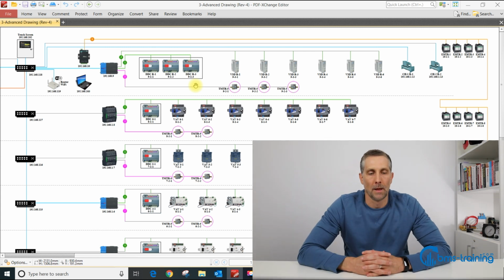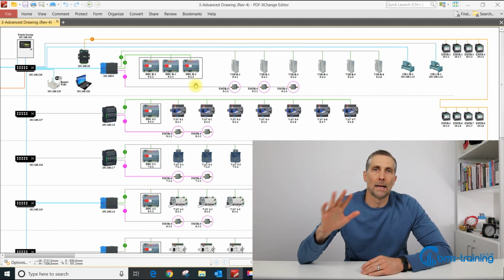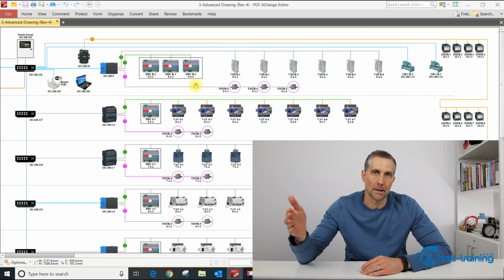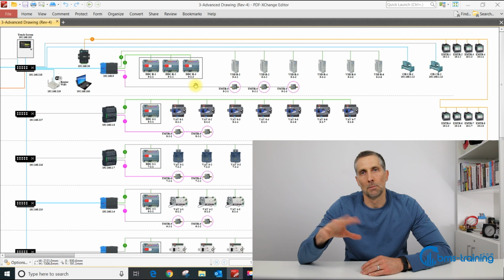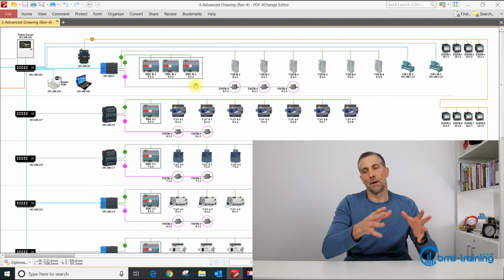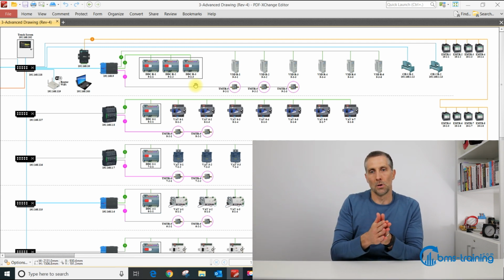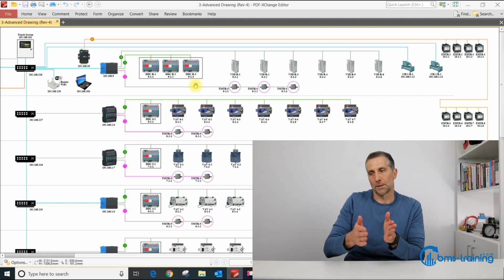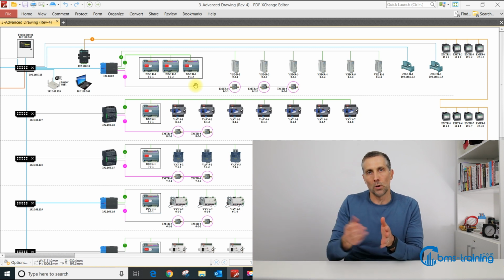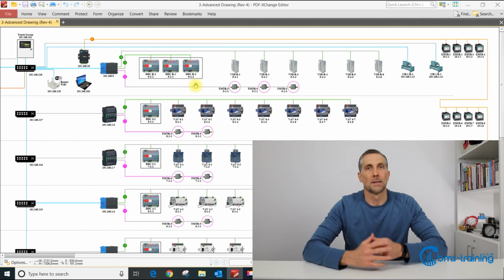Now here are the issues that we normally come across. The first issue is, how does BACnet work? So MSTP stands for Master Slave Token Passing. And this means that the master is usually the network controller, and then all the devices down are the slaves. So this token gets passed down the subnetwork, and only when you have the token can you communicate.